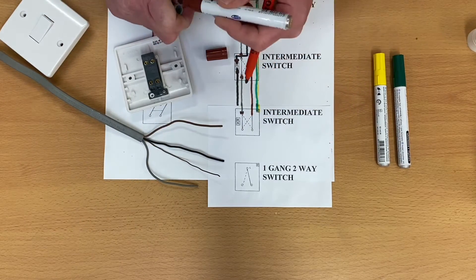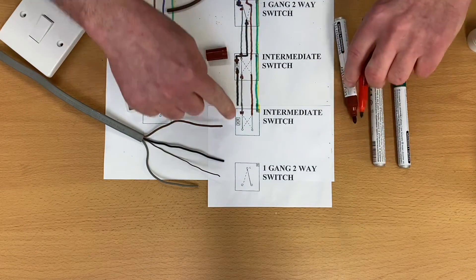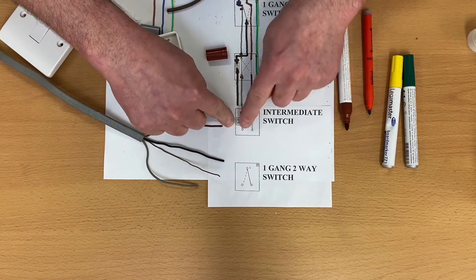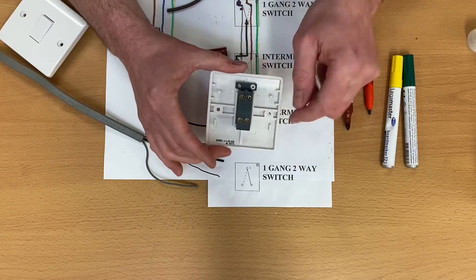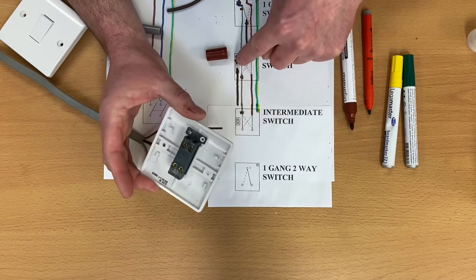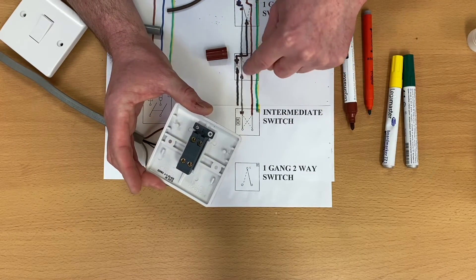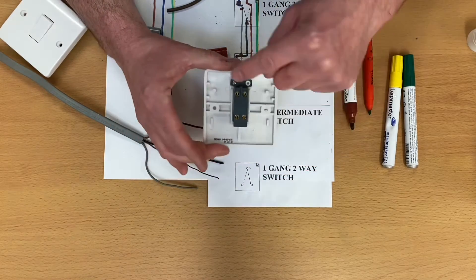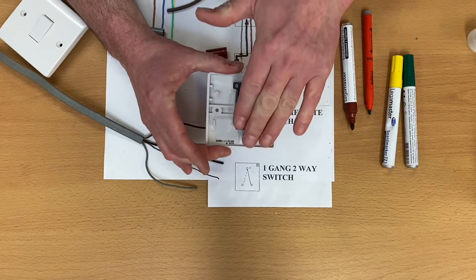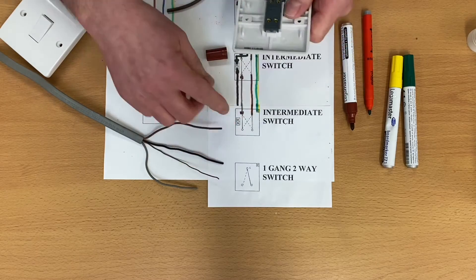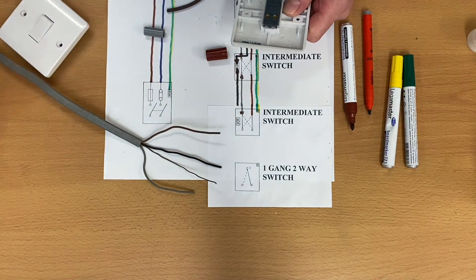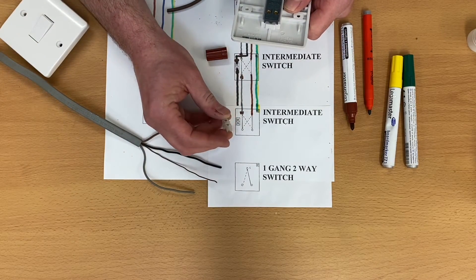So we'll introduce, well, it's probably still on the cable, isn't it? Our brown sleeving. And now we've got another connection, haven't we? Because we know an intermediate switch has our four connecting points. The black, which is our common in our two-way circuit. The common one comes and passes through our intermediate switch. It isn't connected in any of the terminals. It passes through.